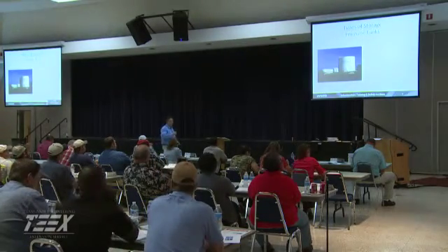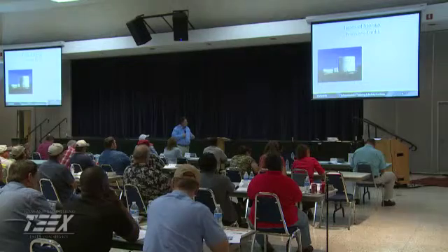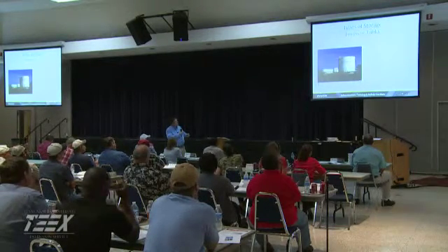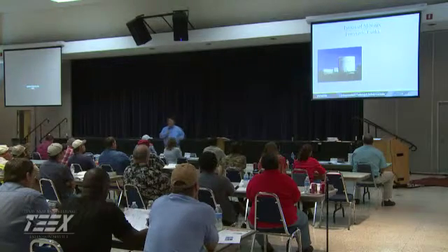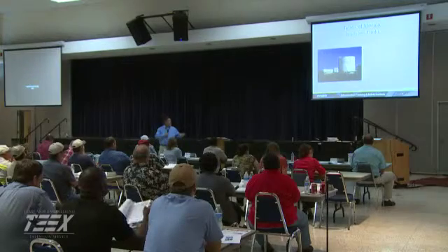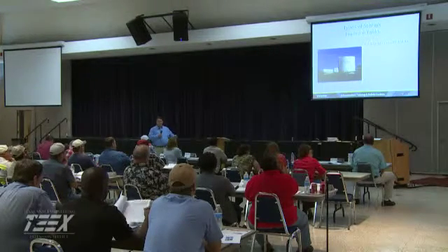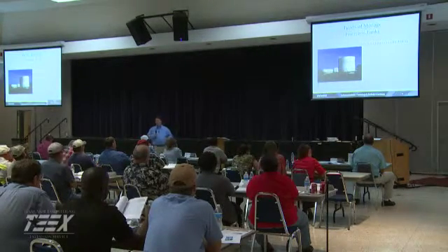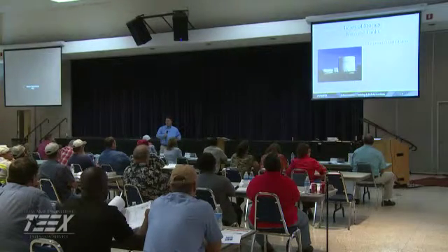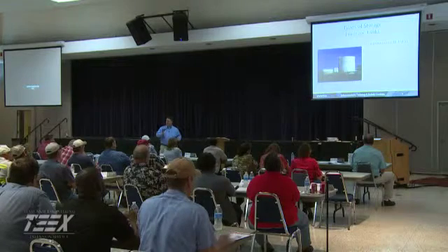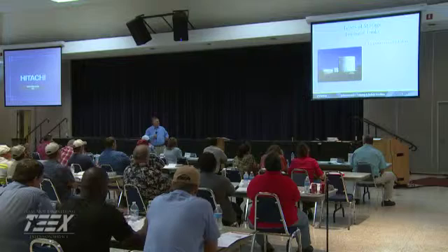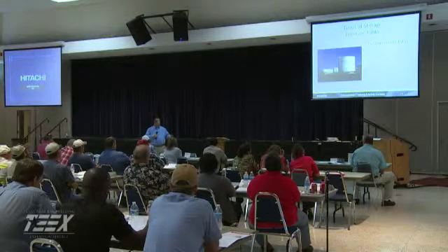All right, pressure tanks. Right down there in the bottom corner, sitting out in front of the ground storage tank, that horizontal thing that looks like a propane tank, that's what we call a pressure tank. Basically, it's a mixture of air and water inside the tank that's used kind of like a shock absorber on your system. You fill it up partially with water, you top it off with air, that air compresses that water, helps keep a nice even pressure out in your system.